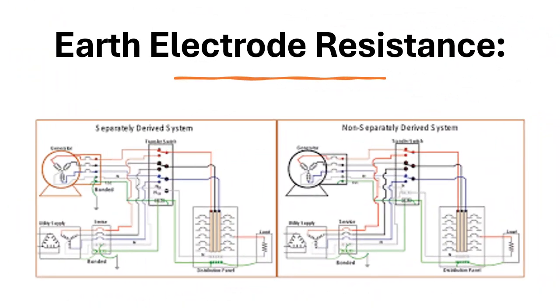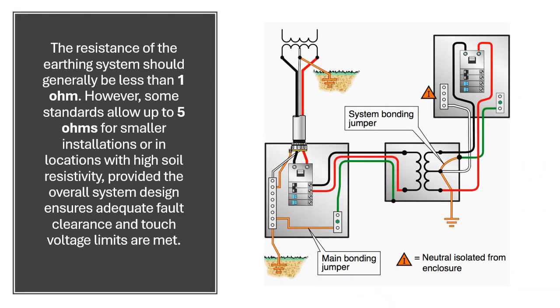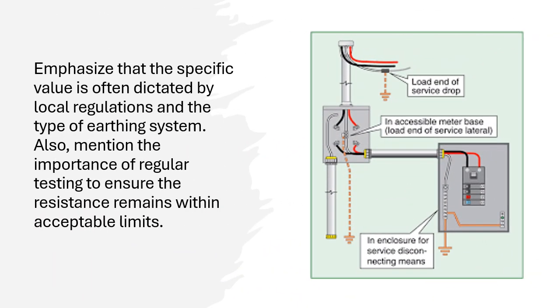Earth electrode resistance. The resistance of the earthing system should generally be less than 1 ohm. However, some standards allow up to 5 ohms for smaller installations or in locations with high soil resistivity, provided the overall system design ensures adequate fault clearance and touch voltage limits are met. Emphasize that the specific value is often dictated by local regulations and the type of earthing system. Also, mention the importance of regular testing to ensure the resistance remains within acceptable limits.